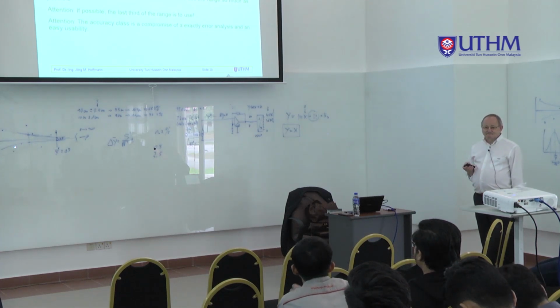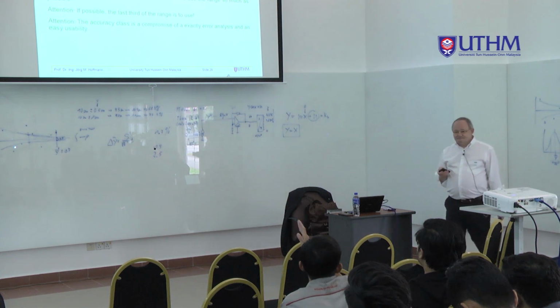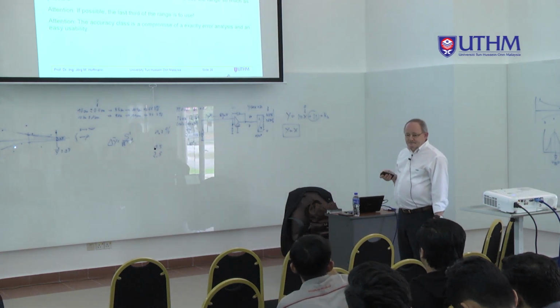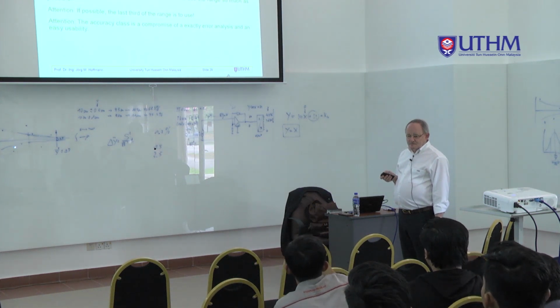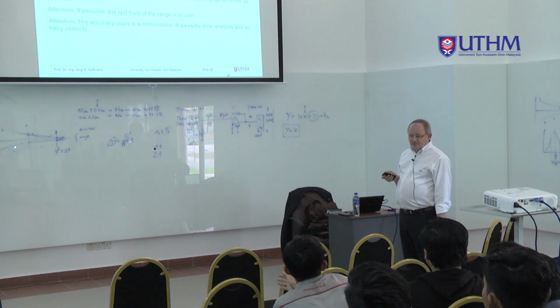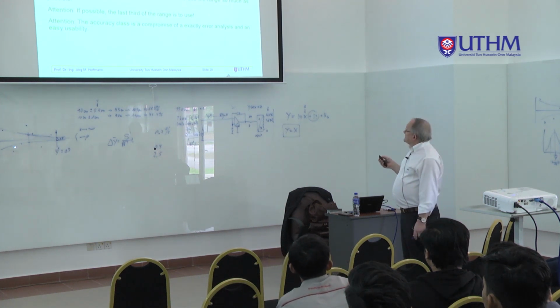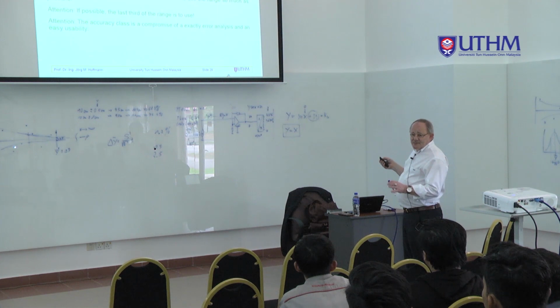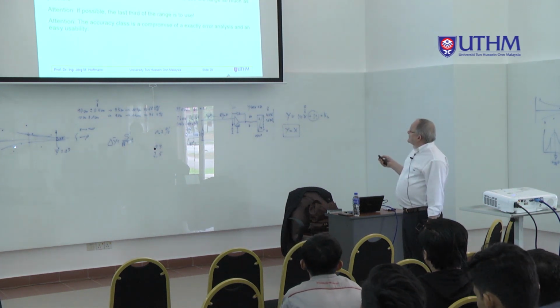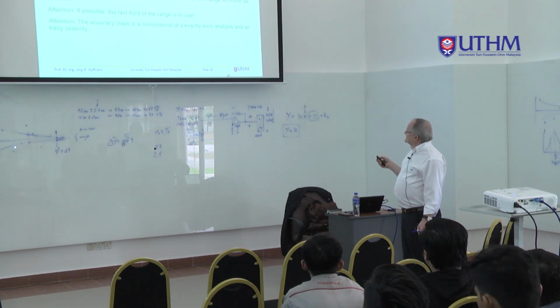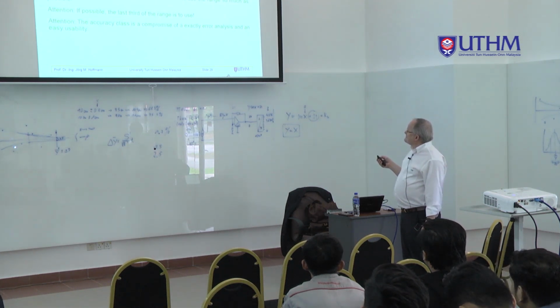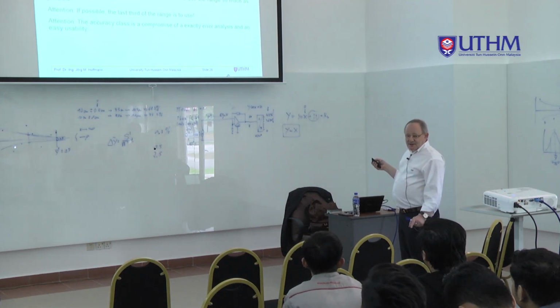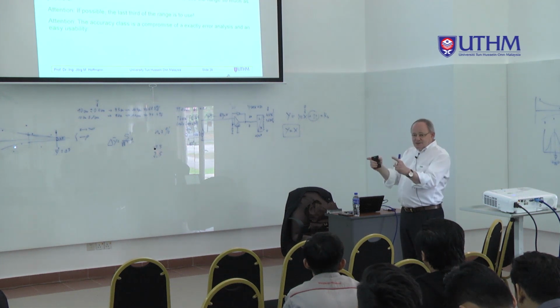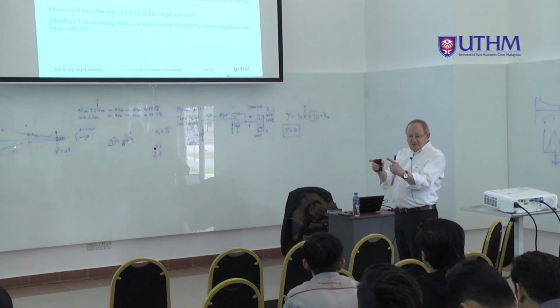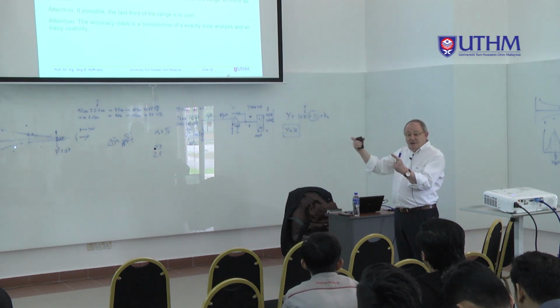Questions? So using the 1% range, you can use it, but then you'd repeat with the standard deviation to correctly calibrate your sensor? No — this is only 1% or 1.5%, that's different, depending on the device. The difference is the company says you will never measure a bigger error than that. The standard deviation says that within this range are 68% of the measurement values, but 32% can also be outside.